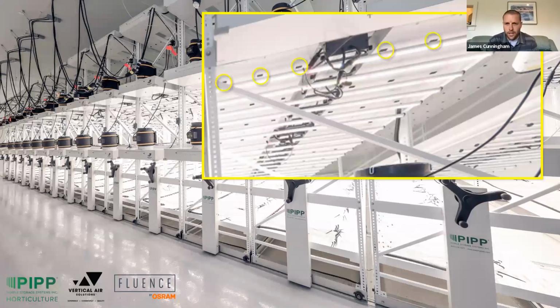As you can see on the mixing chamber there, you can see just a bit of that barbed fitting, which is your CO2 input to inject CO2 into your airflow so that you can have enriched CO2 concentrated air as your room is saturating. Gas spreads relatively quickly in the space, but just like conditioned air, it has a difficult time breaking through barriers. So strategically supplying that CO2 into your air circulation system will keep your CO2 concentrations adequate tier to tier.